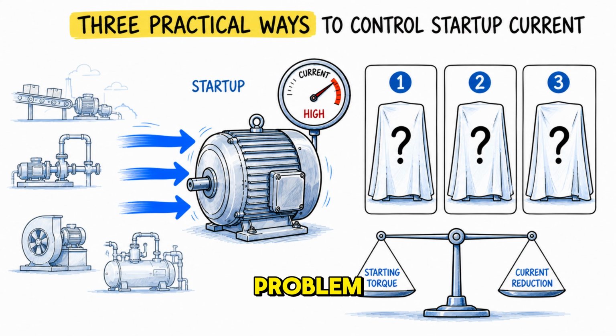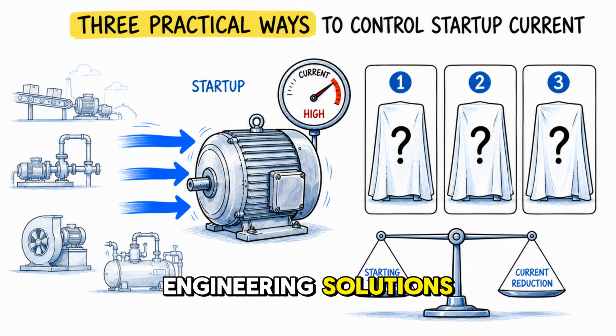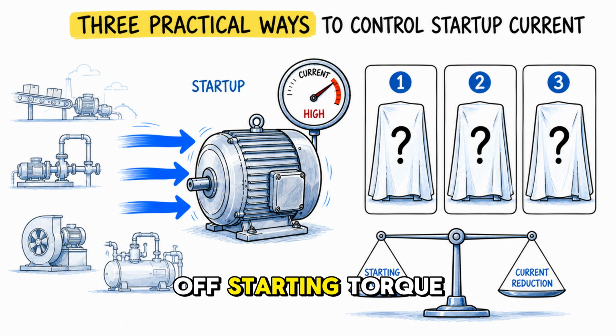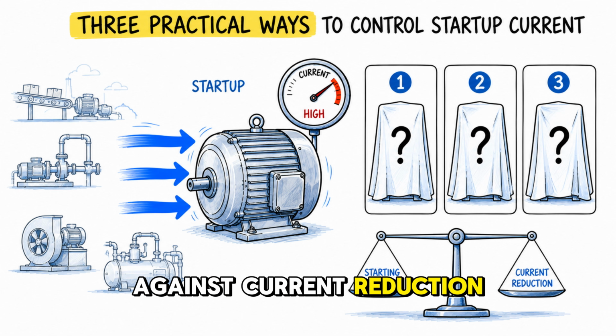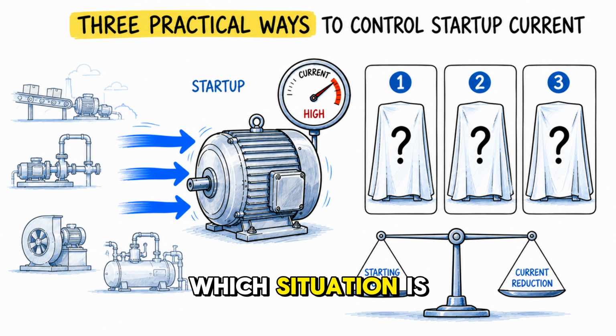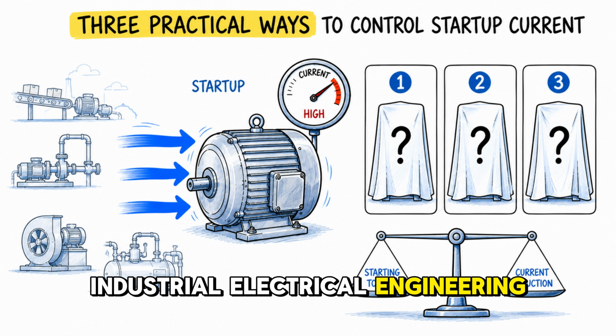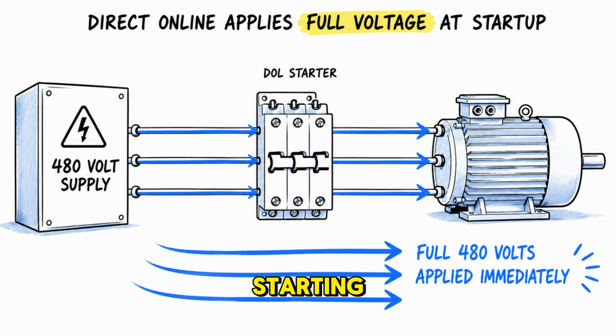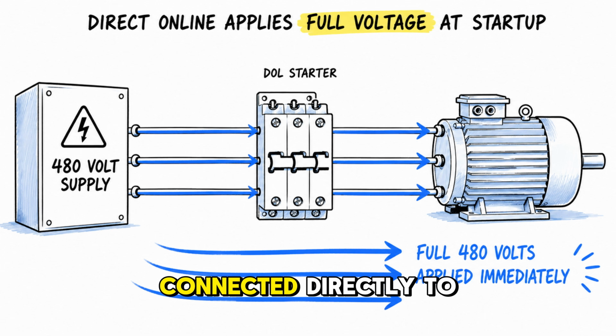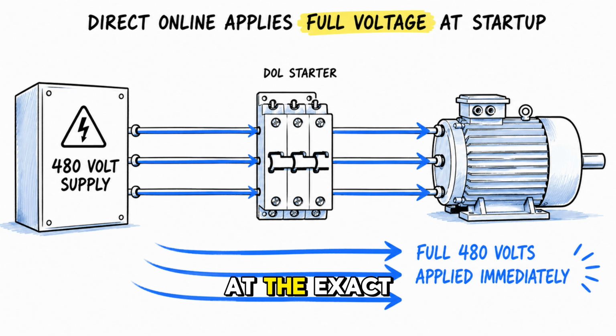The startup current problem has 3 practical engineering solutions. Each one trades off starting torque against current reduction. Understanding which to use in which situation is one of the most practical skills in industrial electrical engineering. The first method is direct online starting, or DOL. The motor is connected directly to full supply voltage at the exact moment of starting. Full 480 volts are applied immediately.